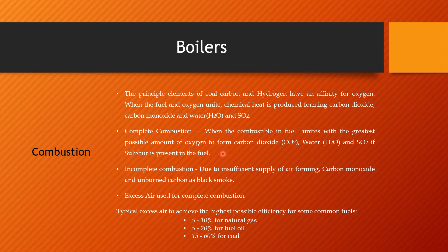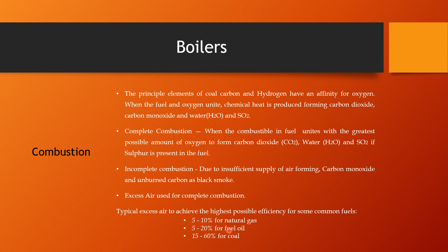In complete combustion, there won't be any carbon monoxide or black smoke — the combustion is complete. In incomplete combustion, due to insufficient supply of air, carbon monoxide and unburnt carbon form as black smoke with the flue gas. Excess air is used for complete combustion. Typical excess air to achieve the highest possible efficiency: for natural gas it is 5–10%; for fuel oil used in a boiler burner it is 5–20%; for coal used in a furnace it will be 15–60%.